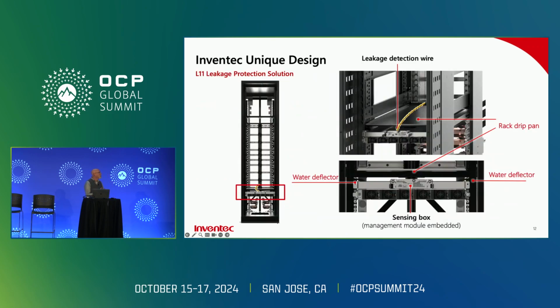Also with rack designs and cooling, there's always leakage and leakage prevention, so we have a unique design for our rack level leakage detection. We do incorporate a drip pan, but we have water deflectors placed throughout the rack and a sensing box at the bottom of the rack.